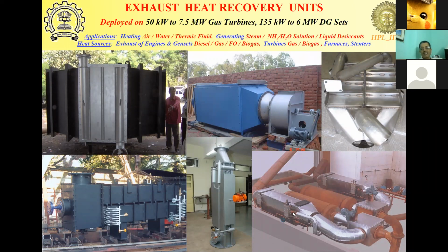Now, as against that, the general conventional engines have exhausts which are very dirty in nature. They are very fouling in nature. They have exhausts which have sticky soot in them. They have unburnt lubricating oil and unburnt fuel at times if the engine is not operated in a properly tuned manner. In such situations, the exhaust gases will be very fouling, and the heat exchangers foul up. If the heat exchangers foul up, the overall heat transfer coefficient goes down, and the heat transfer surface area required is very large. In conventional steam generators for engine exhaust heat, the exhaust heat recovery units are larger than the engines themselves. While in our case, you can see that the exhaust heat recovery steam generator is placed right next to the muffler of that engine. So it's not larger than the engine, but similar to the size of the muffler of that engine.